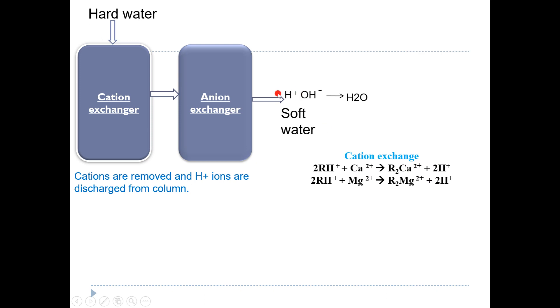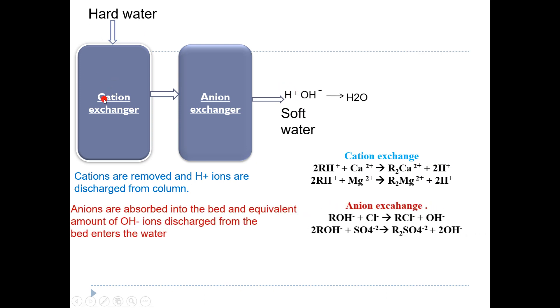After the cation exchanger removes the cations, the water now contains only H+ ions. This water is then passed into the anion exchanger, where anions get exchanged for OH–. The OH– ions present on the resin are exchanged by other ions like chloride, sulfates, and nitrates. This is the only process where anion exchange also takes place — unlike the previous two water softening processes.